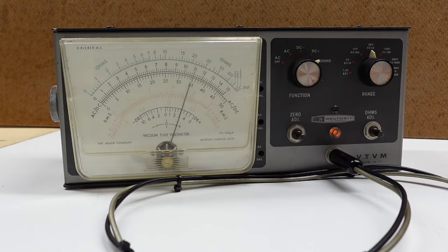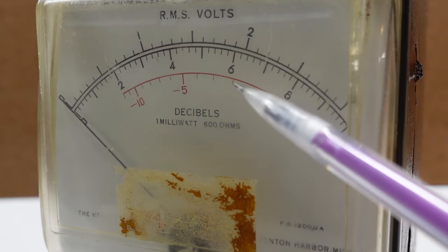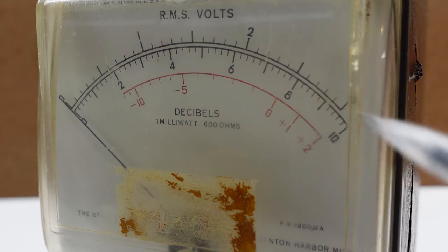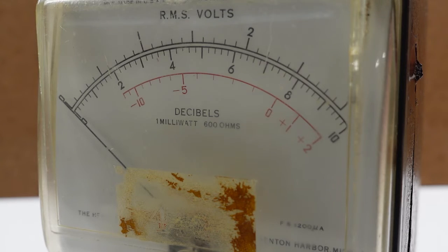But on those occasions where I may actually want to measure a quantitative change, the meter does have a logarithmic scale in addition to the linear scale, which is really nice for tuning a circuit for a relative drop in dB. So that's the first and most obvious item on the scope of work, restoring the meter back to full functionality.